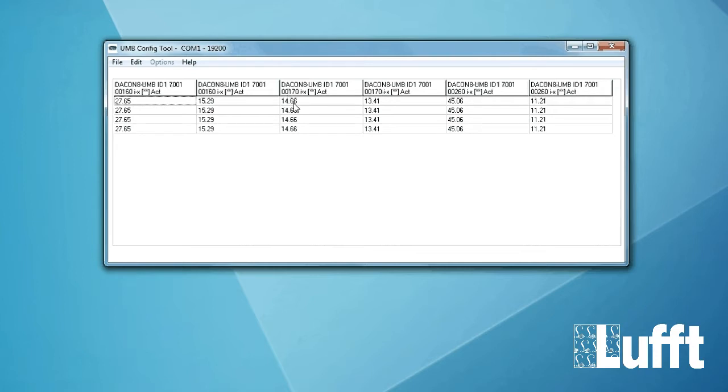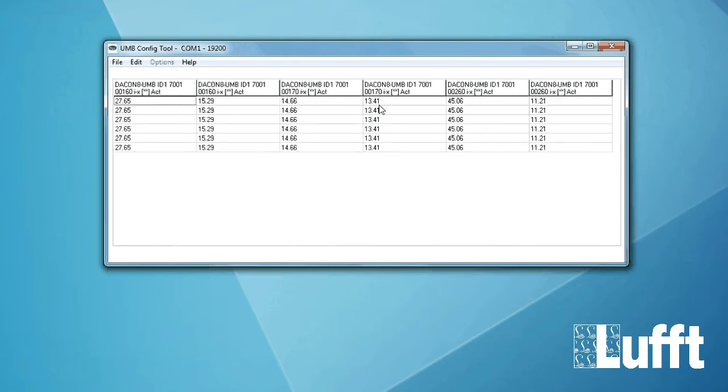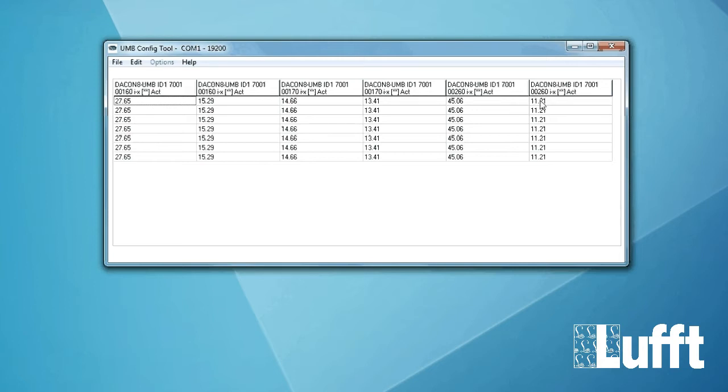Then we have the dew point. 14.66 Celsius degree dew point. And the current output of 13.41 milliamps. And the relative humidity is 45.06%. And we have the milliamp output 11.21 milliamps.